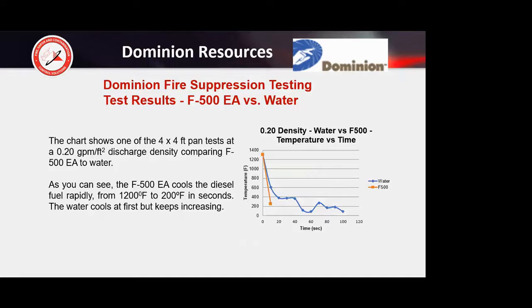I had another graph too showing the water usage. Very interesting because at a higher density of water in the time frame, they would have used 72 gallons of water versus only 8 gallons with the F500 at the lower density. So they were saying, okay, that's big because we have to contain, we have to control this water. We're going to have hydraulic oil in the water. We can't allow this to run off, and having 1/9 the amount of water is going to really be a big cost savings to us.